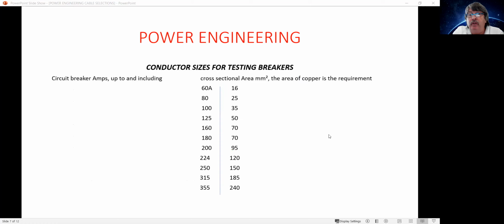Now, we need to have a look then at what we are actually looking at today from the angle we're approaching this. These are the conductor sizes actually specified for the testing of the breaker in the certification phase. So if we're looking at 100 amps approximately, and this is where we said that we would like around 100 amps for our cable, we can immediately see that the PVC cable used for this test of the 100 amp breaker was 35 millimeters squared.